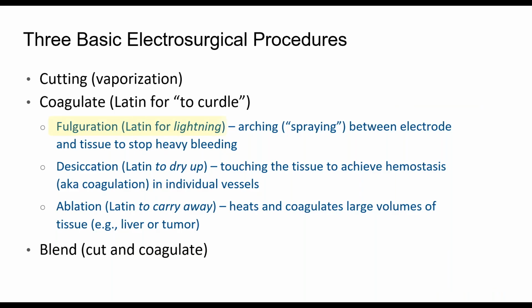Next on here, fulguration, Latin for lightning. Perfect explanation for that. Because as we use the pencil, we hold it up off of the tissue and we allow it to spark down. What it's looking for is the path of least resistance. We know that in electronics, that's what you're looking for. When they hold that up, the path of least resistance it's looking at is what? The blood. So when it seals it here, done.